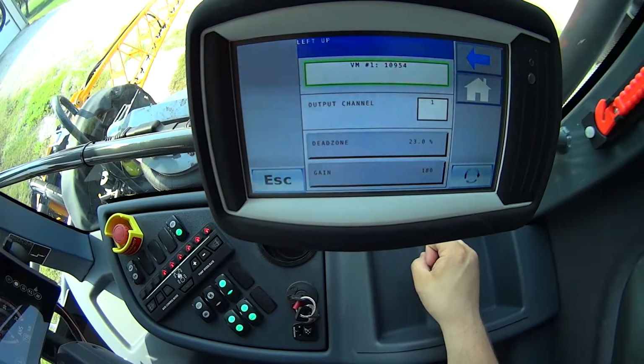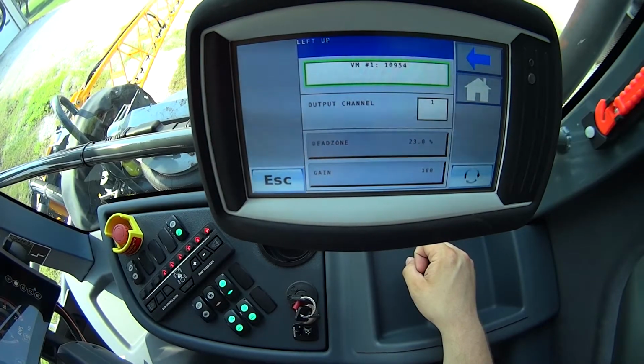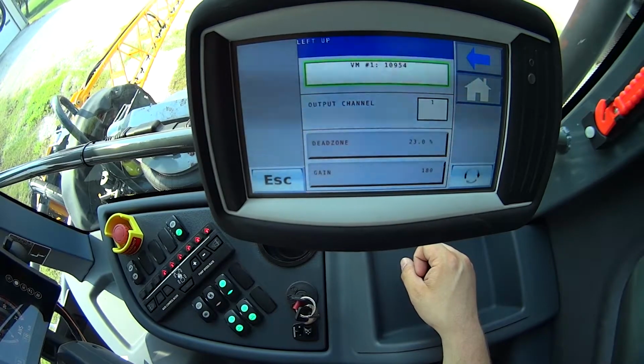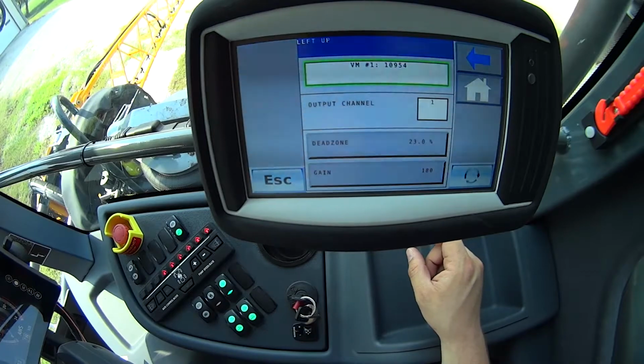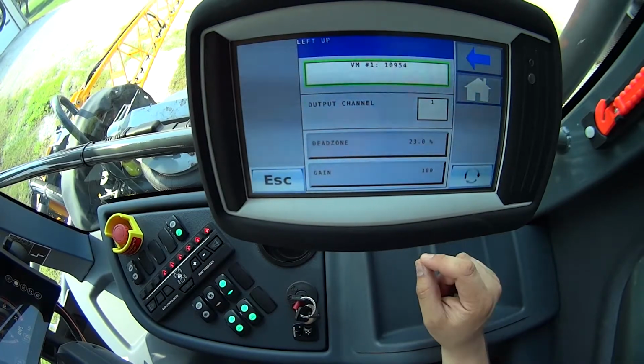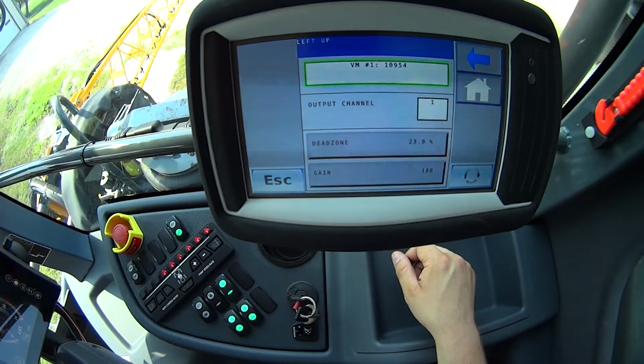Gain value. Gain value is probably most closely related to an aggressiveness factor. So how hard I drive that valve. The dead zone's the minimum amount I have to do to get that to move, and the gain is more the aggressiveness. In this case, it's set to 180. We do default these values from the factory at that 180. We find that that works very, very well on these booms, and have done a lot of testing on that value. However, that can be adjusted.